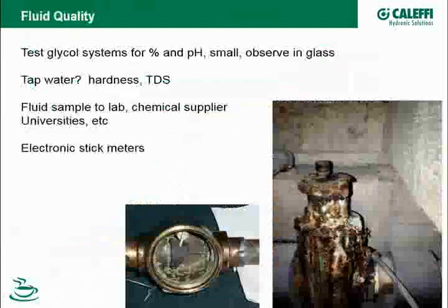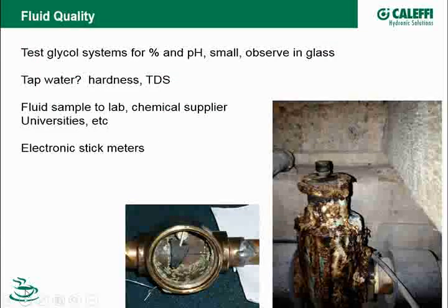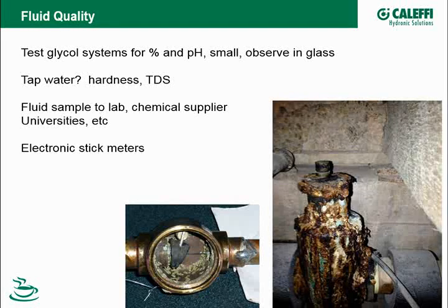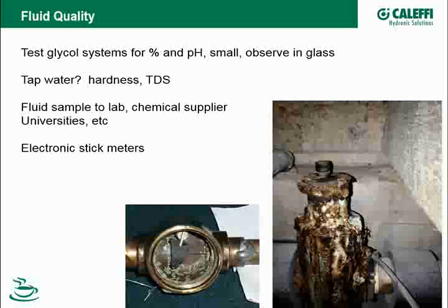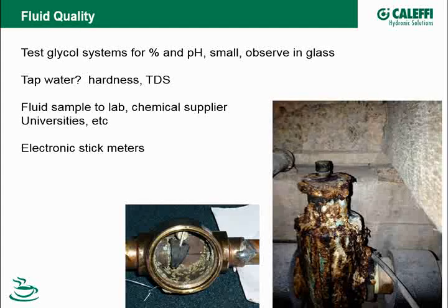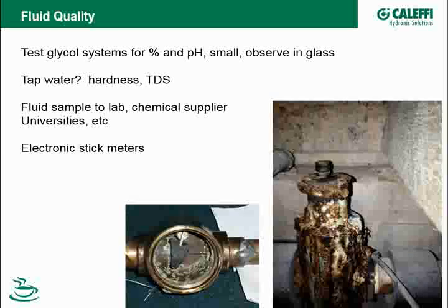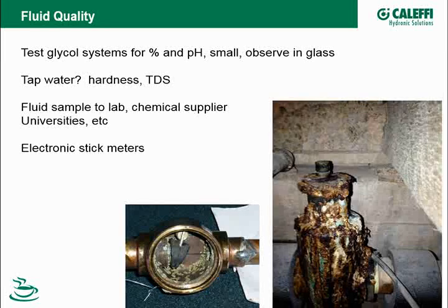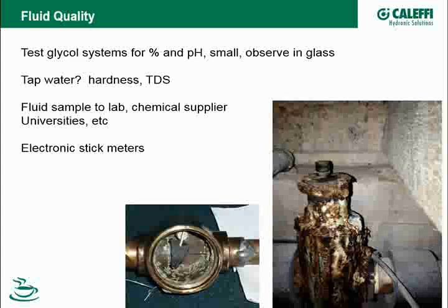Fluid quality. This thing comes up a lot, and it's coming up more and more often. I don't think a lot of people realize what's going on with the system fluid and how critical it is to not only the heat exchange ability of the thing. If you've got a buildup of lime scale or calcium inside your heat exchanger, the efficiency of that device is really starting to drop, and it doesn't take much. I mean, we're talking a millimeter or two thickness can really start changing the heat transferability of a heat exchanger, and that's true in the boiler as well as the heat emitters.